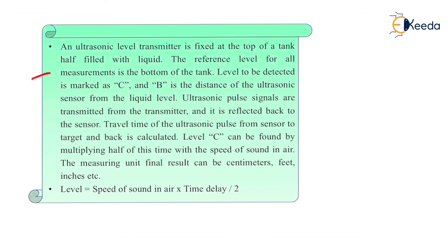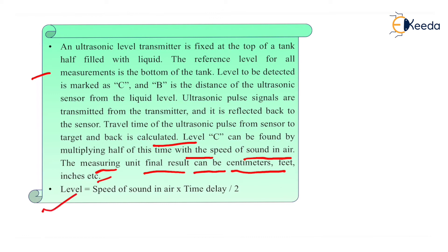Ultrasonic pulse signals are transmitted from the transmitter and reflected back to the sensor. The travel time of the ultrasonic pulse from sensor to target and back is calculated. The level C can be found by multiplying half of this time by the speed of sound in air. The level can be calculated as: Level = (speed of sound in air × time delay) / 2. The measuring unit can be centimeters, feet, or inches.